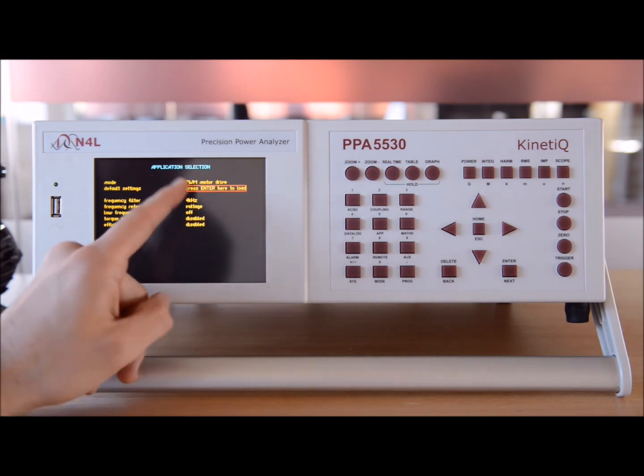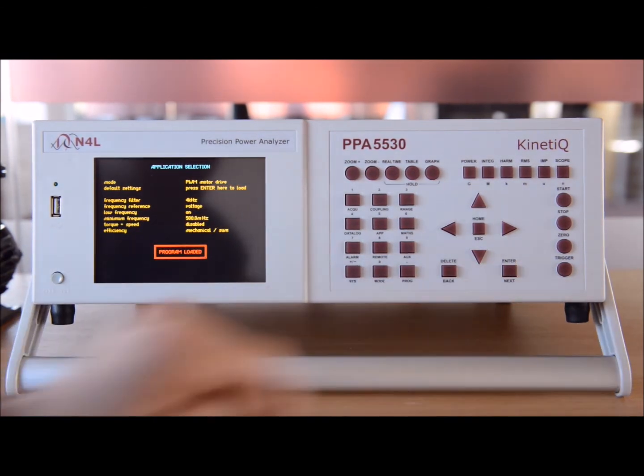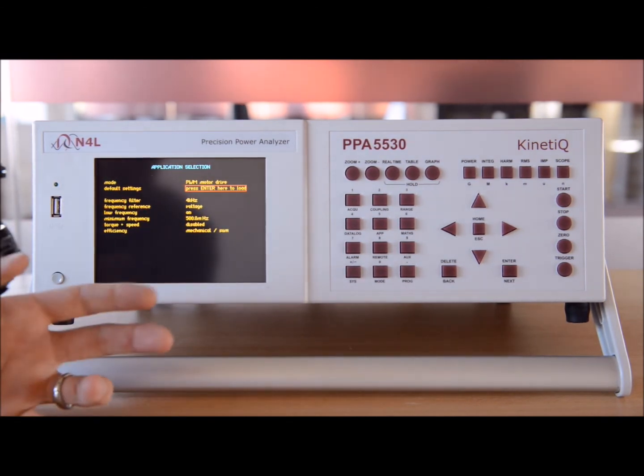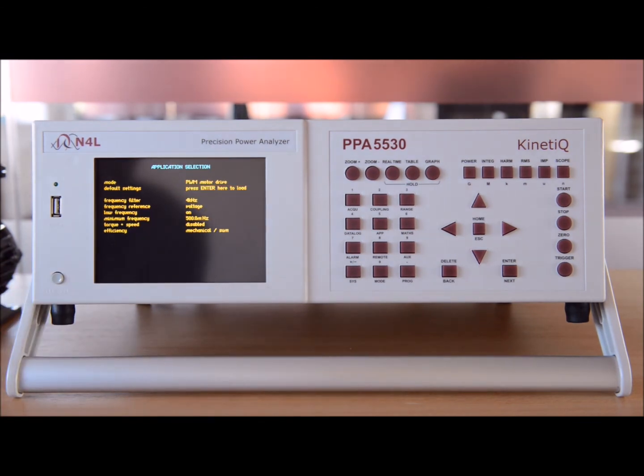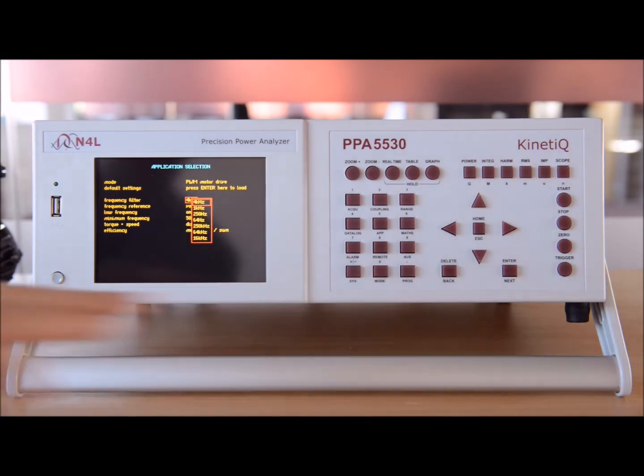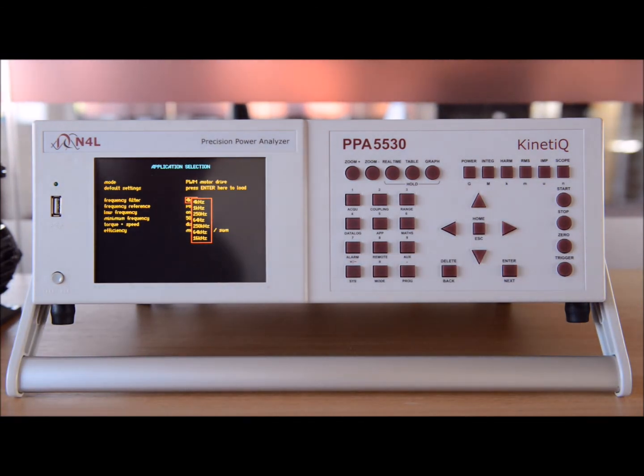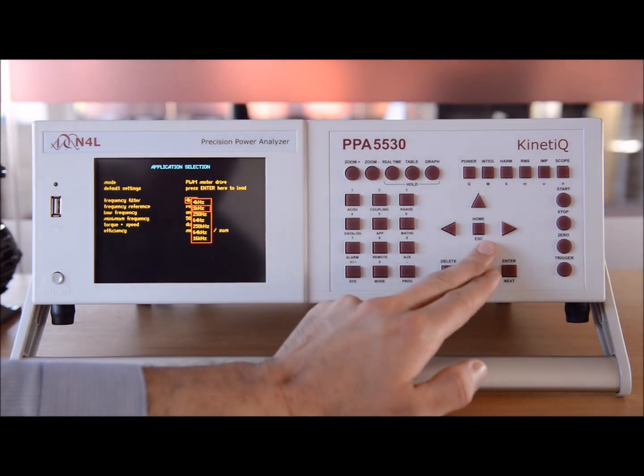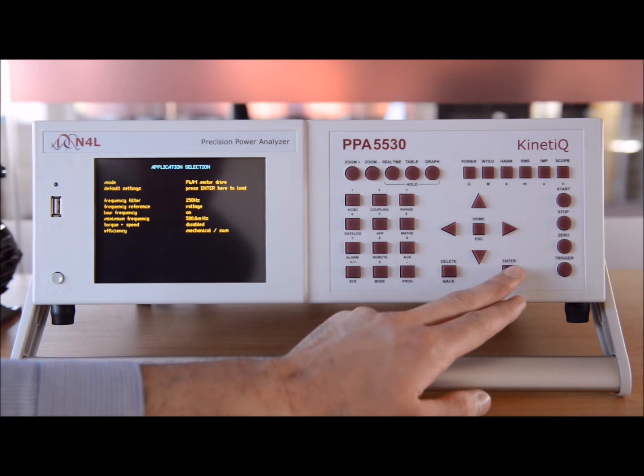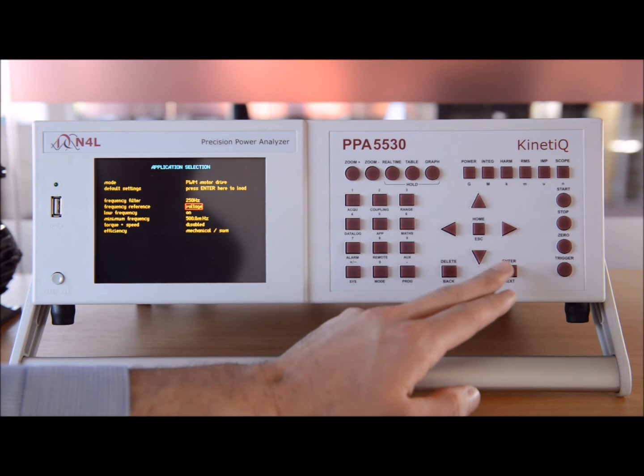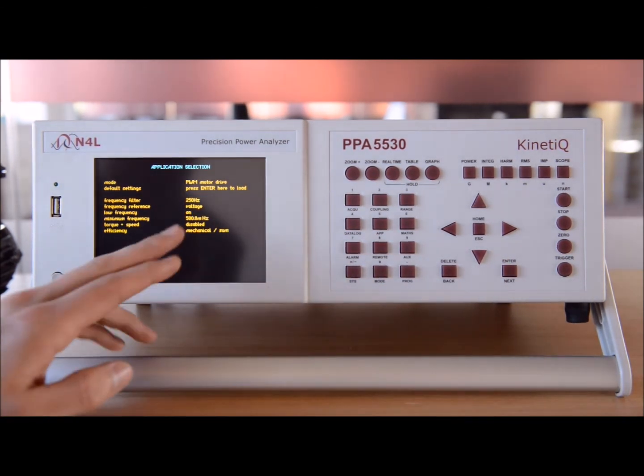After we select a mode in the PPAs, what we always do is go down to the next line, default settings, press enter. And what that basically does, it selects some suitable settings in the background optimized for PWM motor drive measurement. Now, as we discussed, the switching frequency, approximately 7 kHz, and today our uppermost motor frequency measurement is going to be around about 100 Hz. And the rule of thumb here is to use a frequency obviously in between the switching frequency and the motor frequency, but I always veer closer to the motor frequency. It just gives us better frequency synchronization. So if I select 250 Hz, which is well above the 100 Hz uppermost motor frequency and well below the switching frequency, what we have here is frequency reference.